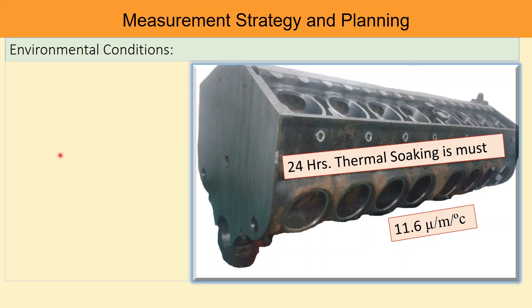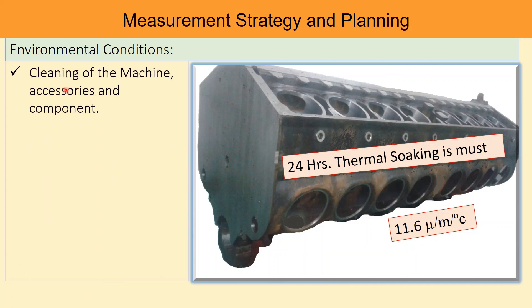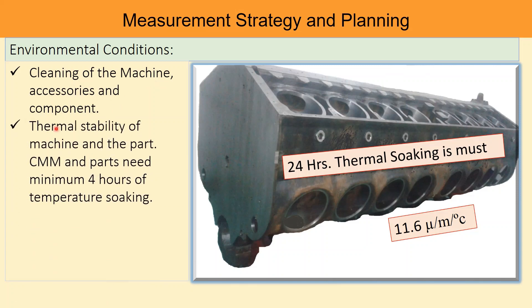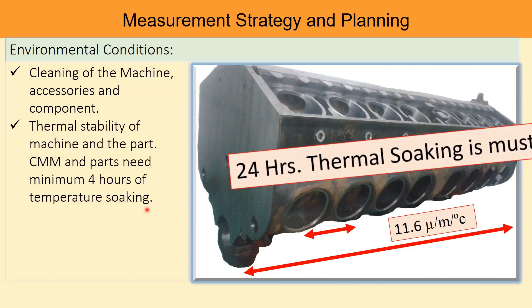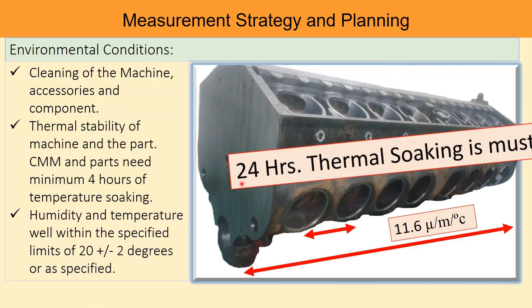Environmental conditions are also critical: cleaning of the machine, accessories, and component; thermal stability of the machine and the part. CMM and parts need a minimum of 4 hours of temperature soaking, and in the case of large parts this may be extended up to 24 hours. Humidity and temperature should be well within the specified limit of 20 degrees ± 2 degrees, or as specified by the manufacturer.